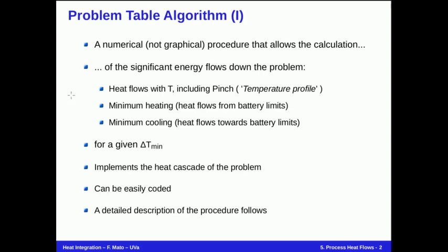These heat flows are the minimum heating that enters the problem at the top from battery limits, the heat flows down with temperature, including the pinch, which is what we will call the temperature profile, and finally the minimum cooling, the heat flow that goes out of the problem towards battery limits. And all these will be calculated for a concrete temperature approach.